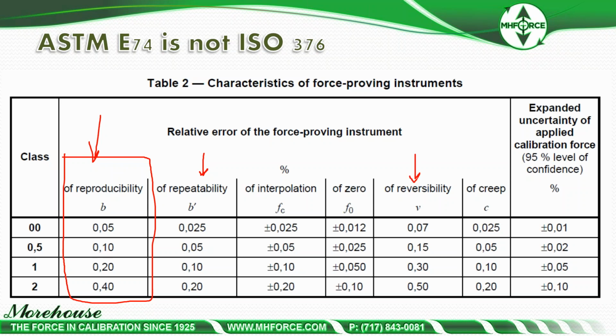That's only if you're using the calibration for descending. And if I back up here, if you're using the calibration for descending, you need to have it calibrated descending. And then if you don't use reversibility, you can do a creep test, and then it has the expanded uncertainty of the applied force. So if my uncertainty, which it is, of our million-pound standard is better than 0.01, I can assign a class 00 range.